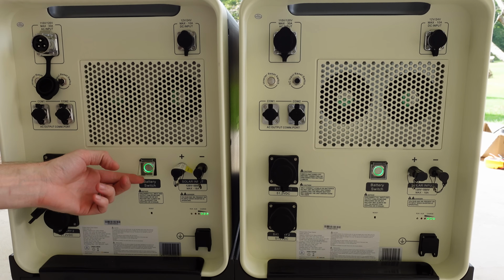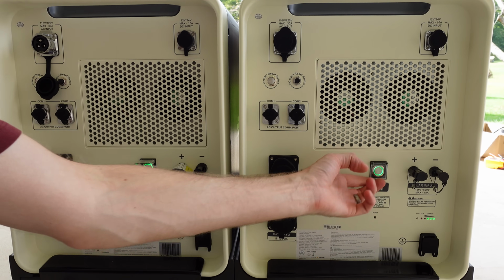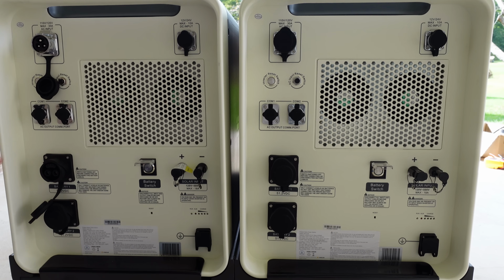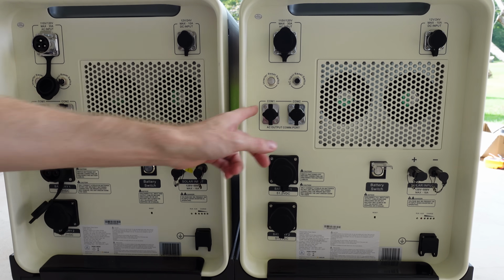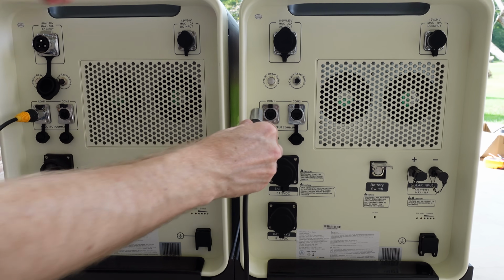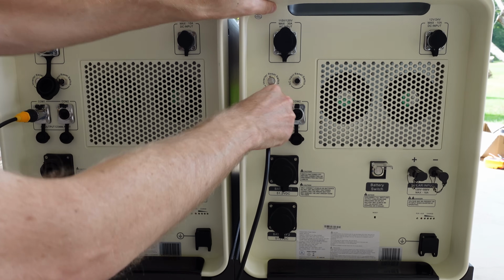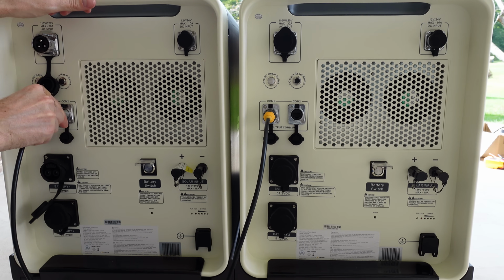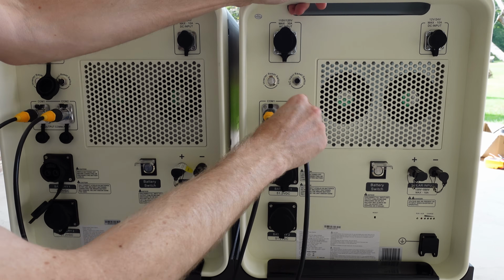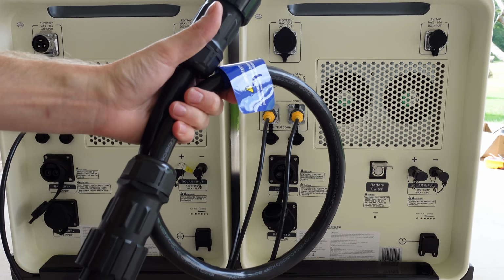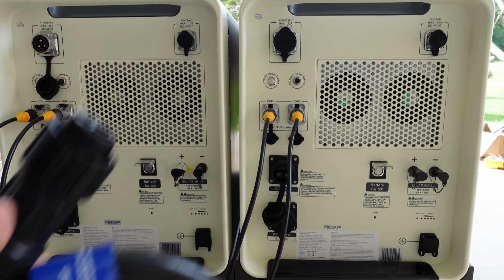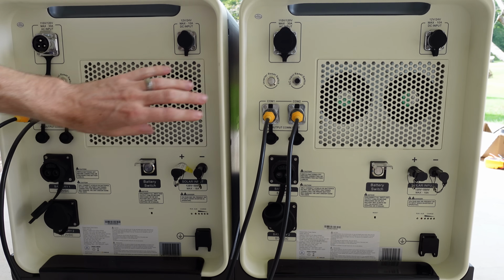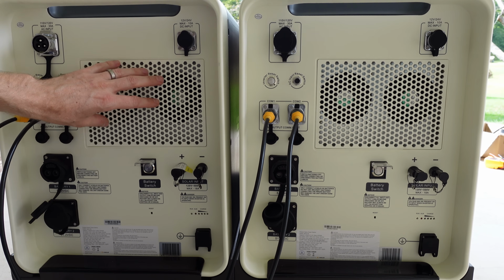Next, we need to switch off the battery on both units. We're going to connect our communications cables first, so COM 1 goes to COM 1 on the other unit, and COM 2 goes to COM 2 on the other unit. Next, we'll connect our battery paralleling cable, and what this is going to do is essentially put both of these batteries into parallel so they're always at the same state of charge.